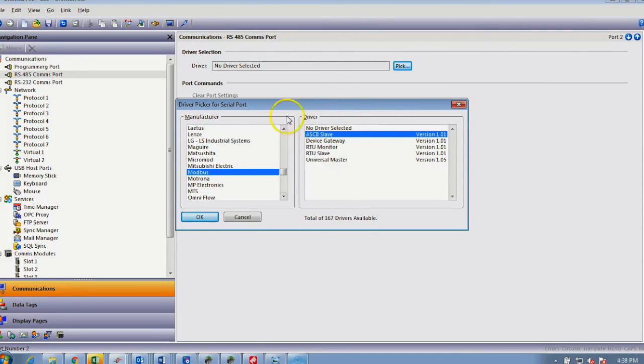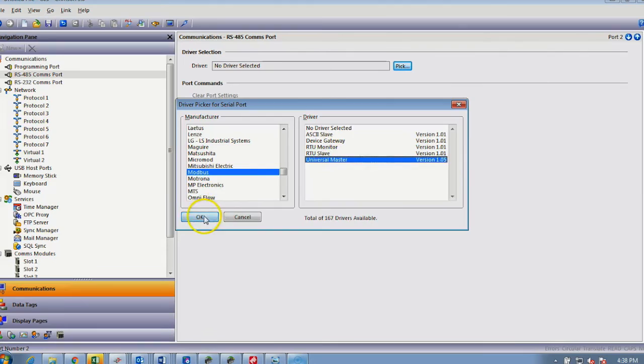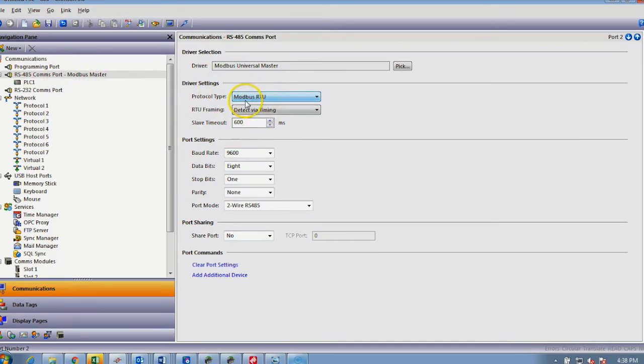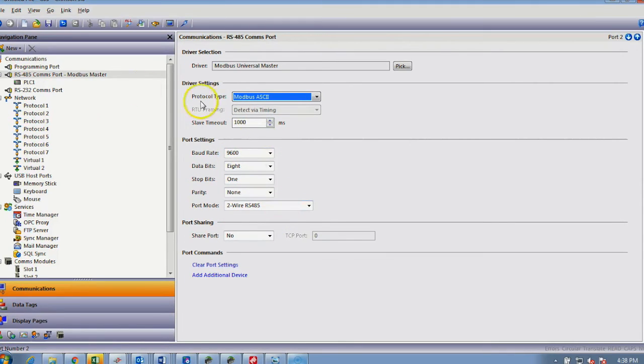For the sake of the example, I'm going to set this particular Graphite up as a Modbus master, in view of it talking to external devices. Quite simply, once you've found your appropriate driver, you adjust the settings of that driver—say, for argument's sake, you're using ASCII, your slave timeout, your speed and your port modes.